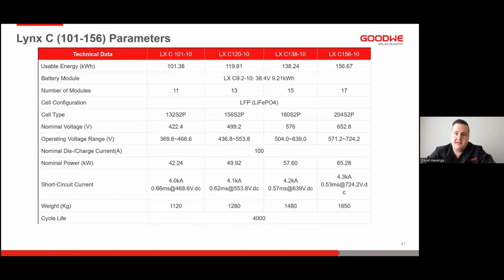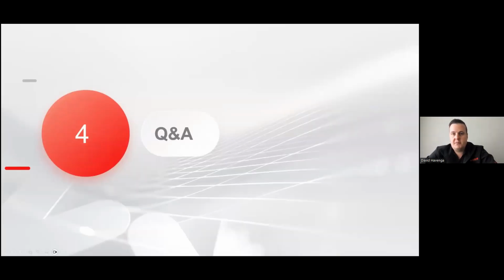Looking at the technical data sheet of the Lynx C, as I mentioned, we do have a 100 and a 120 kilowatt hour battery, but because of the 0.4C discharge rating on the batteries, we recommend the Lynx C138 or the Lynx C156. That's just for the nominal power and the voltage and the discharge limits. I think we'll move now over to the Q&A section.